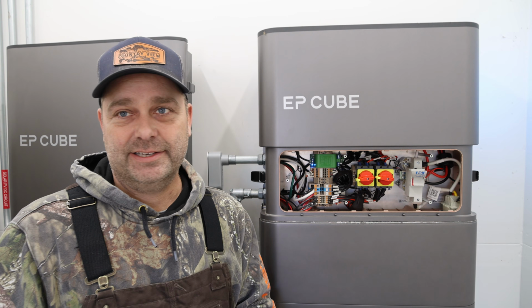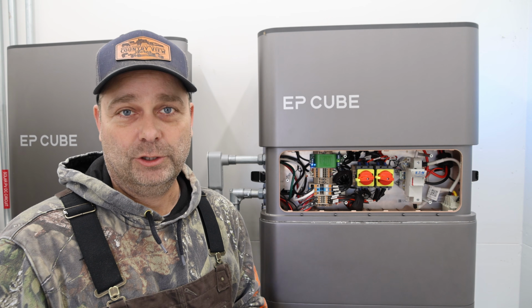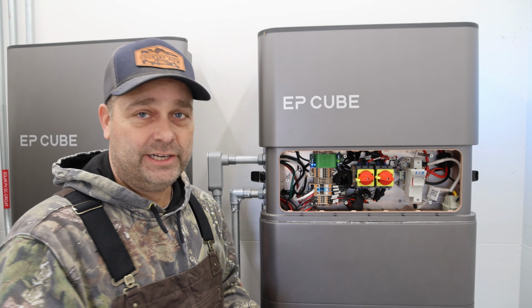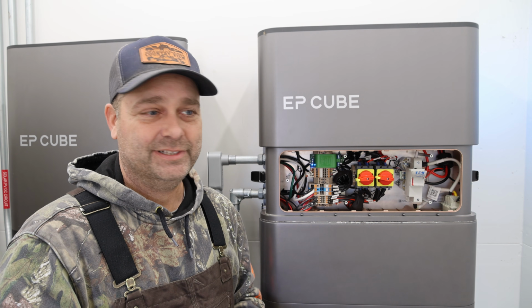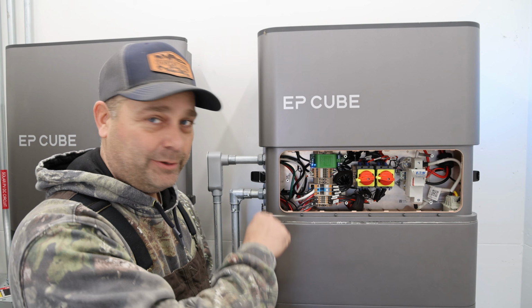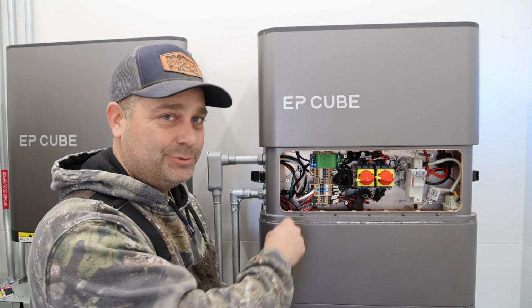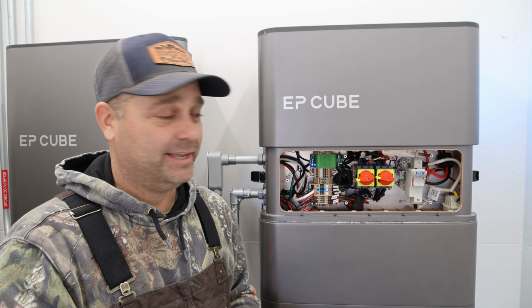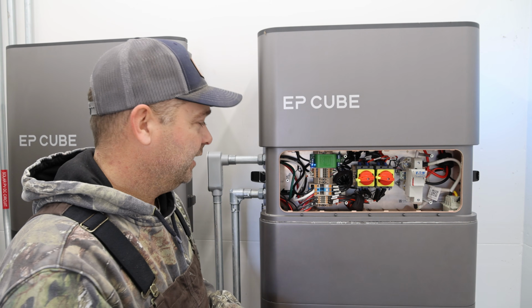So the next thing I did is I decided, well, let's take this good solar array that was running just fine on array number 3. I took it and moved it over to array number 2, and instantaneously started getting problems. So I put it back on array number 3, and it worked fine. I put it back to array number 1 to try it out. Same deal. I kept on getting constant arc fault errors.